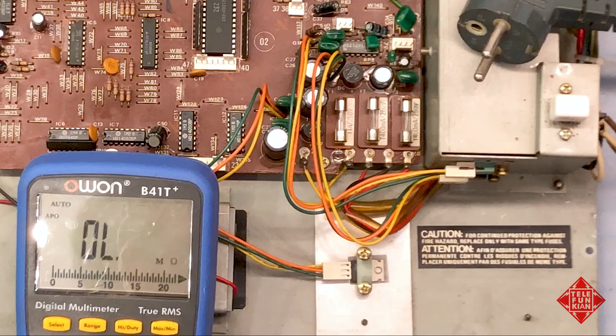If we probe across these two wires, the white and the brown, which go to the transformer, and measure the resistance, we see 152 ohms. That is the resistance of the primary winding, so the transformer is not open.